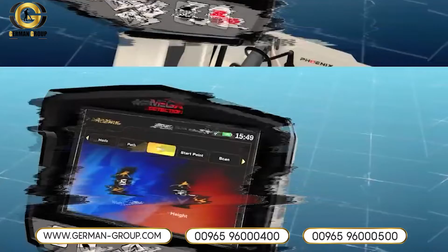And every time the user moves to the left or right, it's called a scan line, meaning he moves to a new scan line. Start point. Here, the user can specify the starting point of the scan within the area, and there are 2 options. Left: the start of the scan is in the lower left corner of the scanning area. Right: the start of the scan process is from the lower right corner of the scanning area. The location of the starting point can be selected using the left-right arrow buttons, then pressing the OK button.